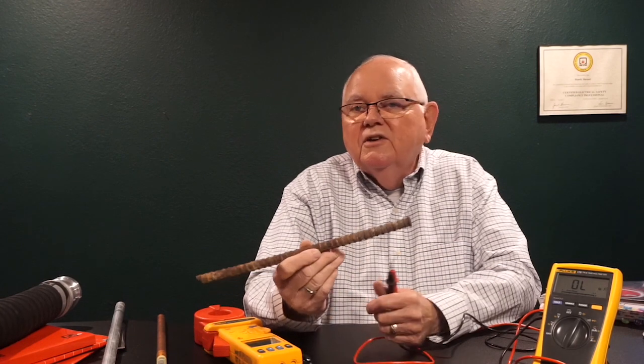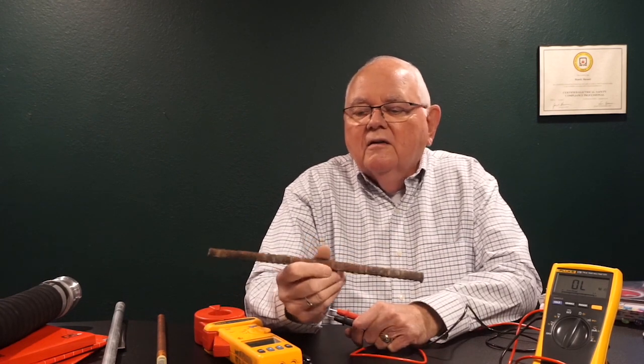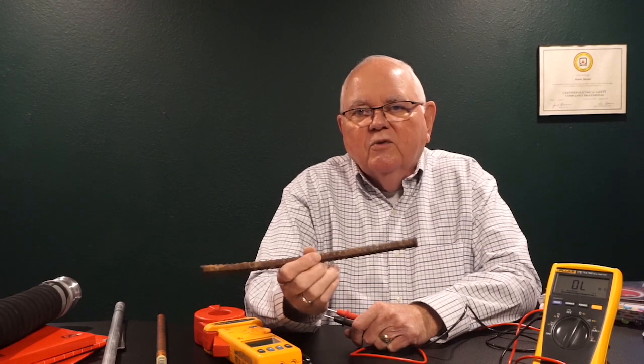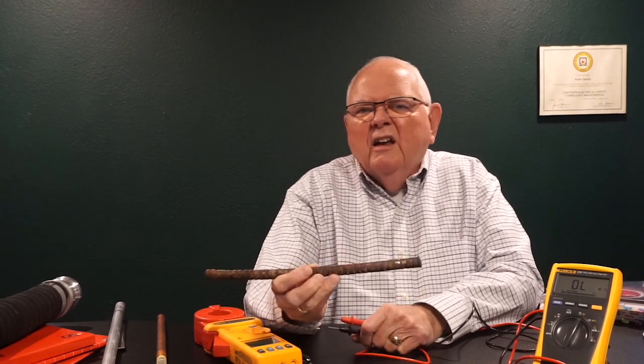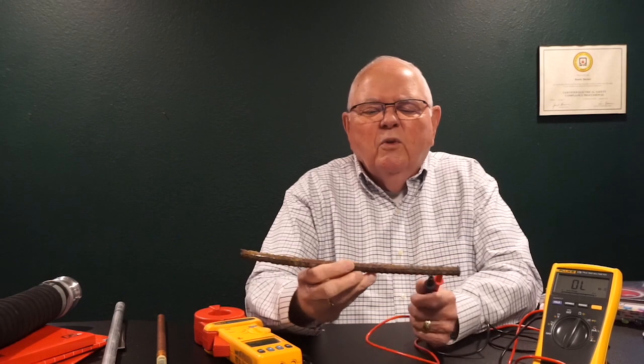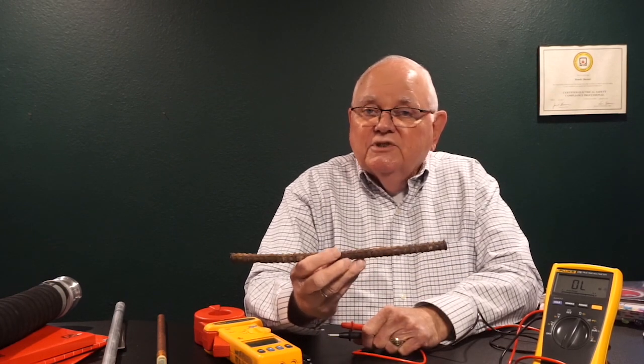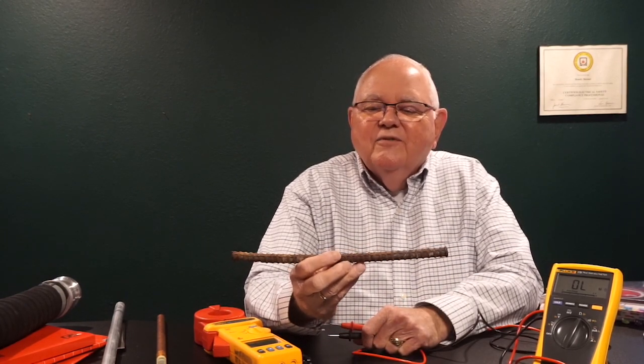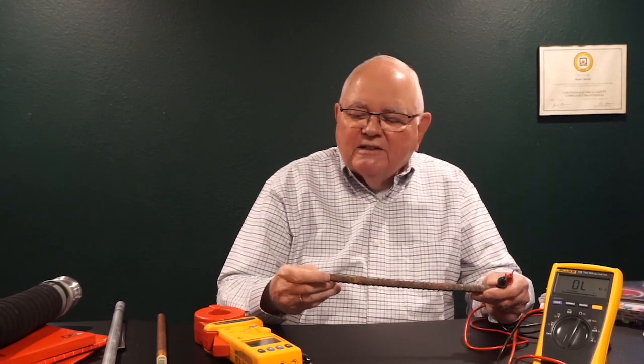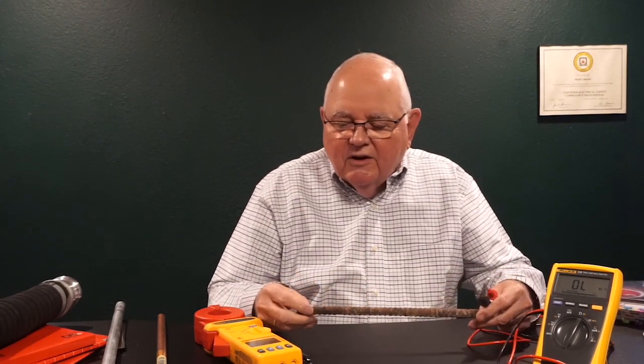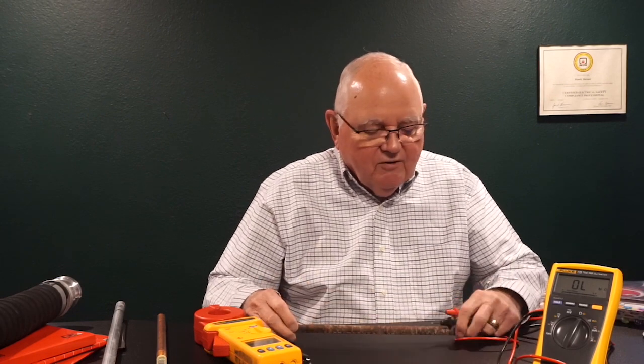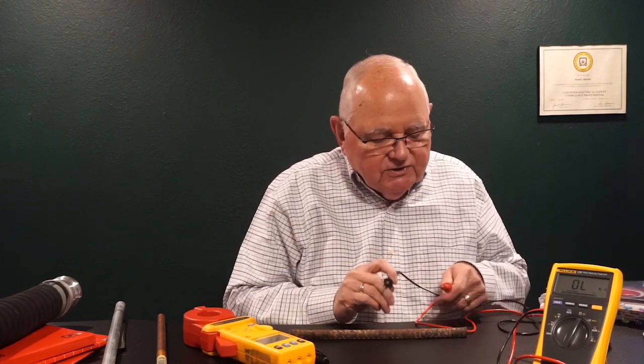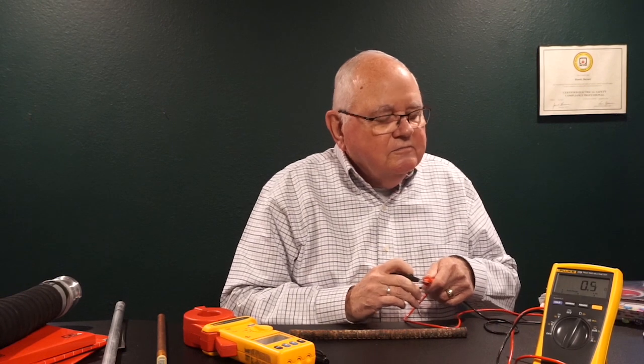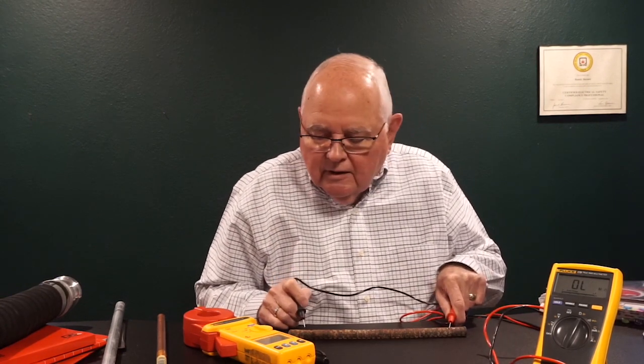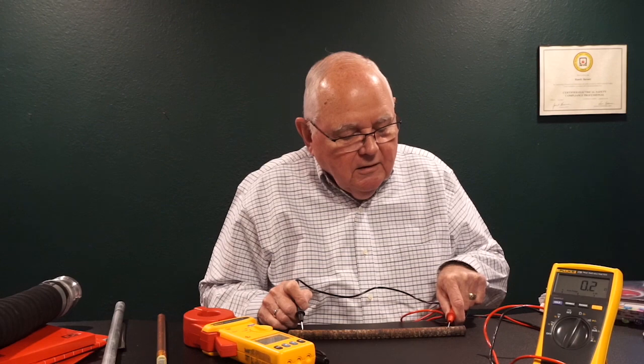It's not conductive. So rust is not conductive. But wait, then you can't use that for, no. Okay, because what happens when I put it in concrete? What's in that concrete? That lime in the concrete. That lye is going to eat away that rust, and pretty soon that rebar is going to be very conductive. In fact, I've got a couple of spots on here, if I can find them. Yeah, there we go, where I've scraped away some of the rust. And let's see what we read on the actual steel here. And yeah, we do get continuity then, okay?